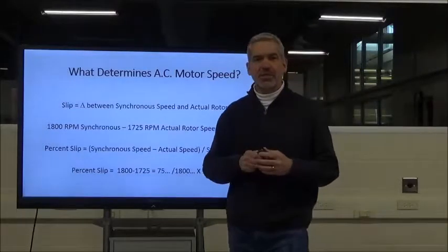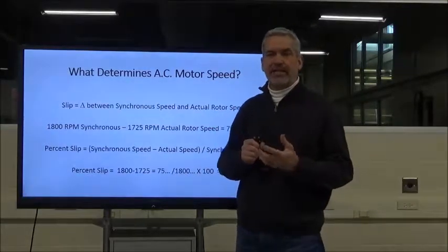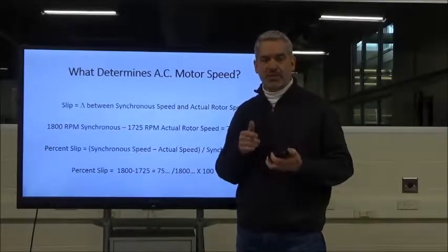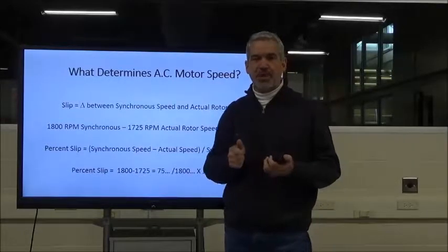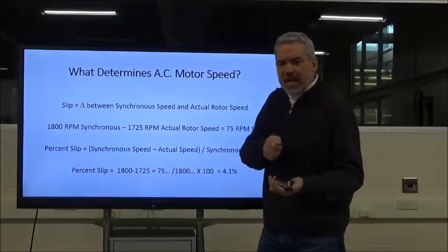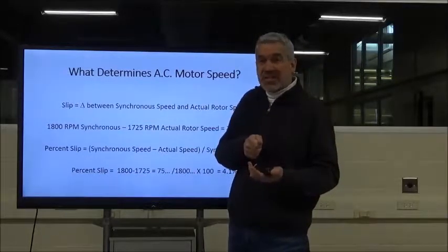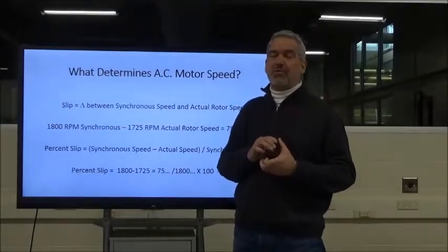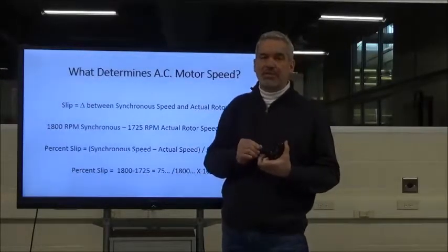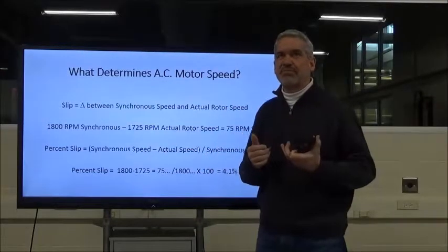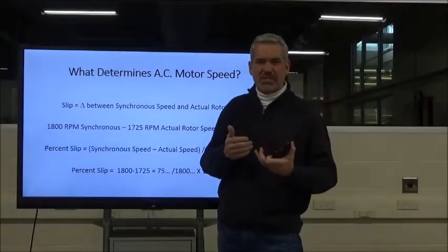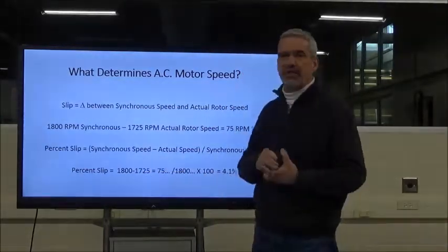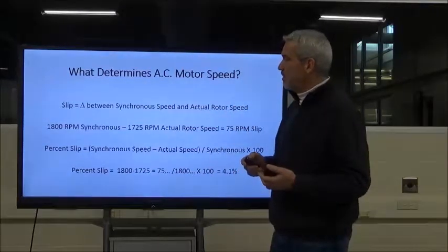In the lab, you'll be asked to point a strobe light at a piece of reflective tape on the motor shaft to measure its actual speed. You'll notice it won't be 1,800 RPM — the actual shaft speed will be somewhere around 1,750 to 1,760 RPM. You'll then calculate the slip and its percentage.